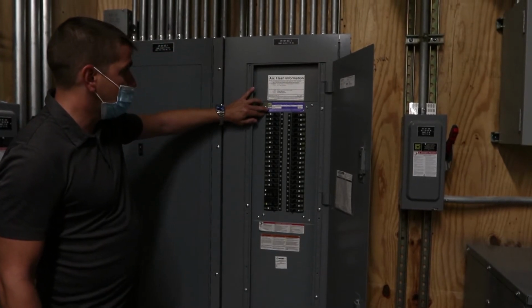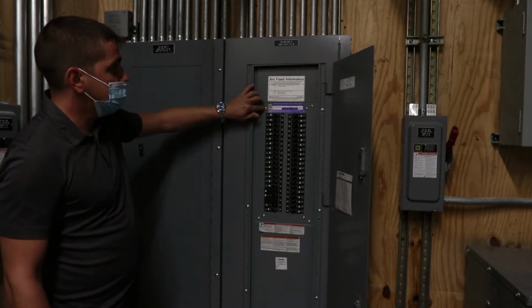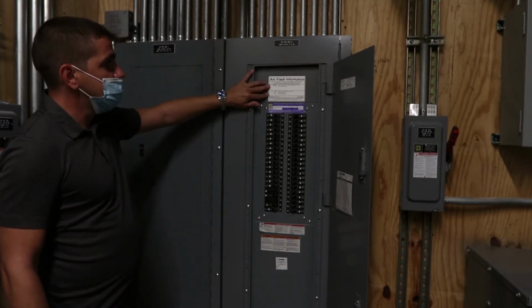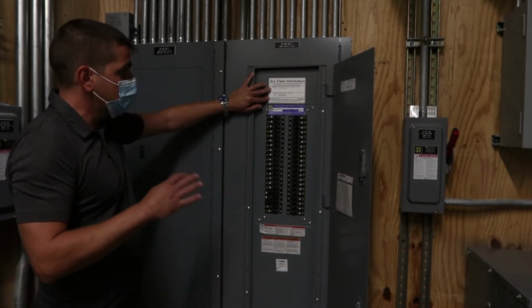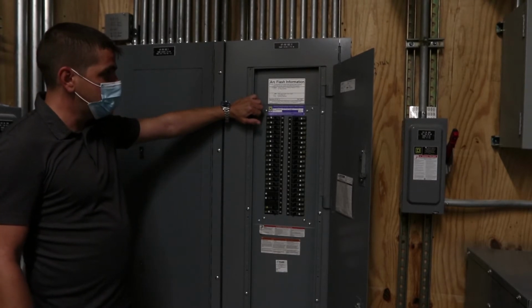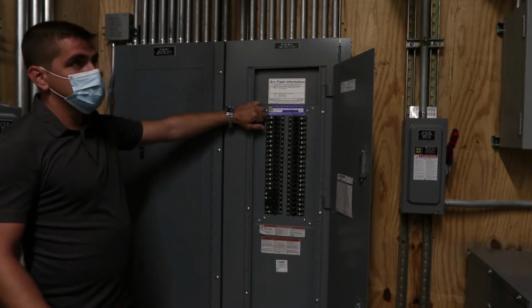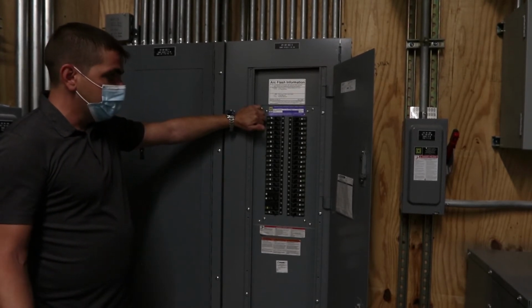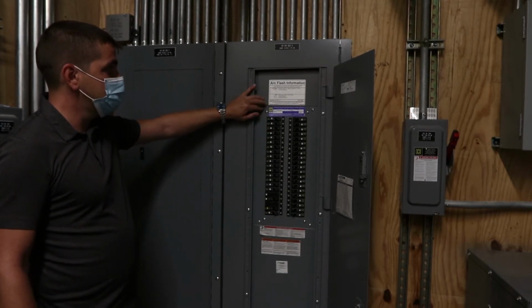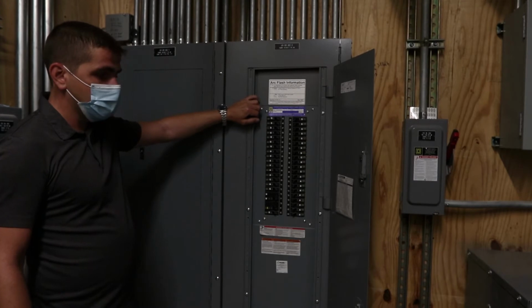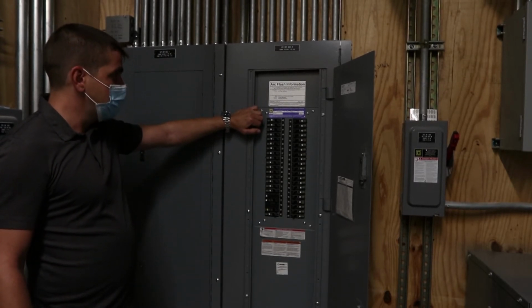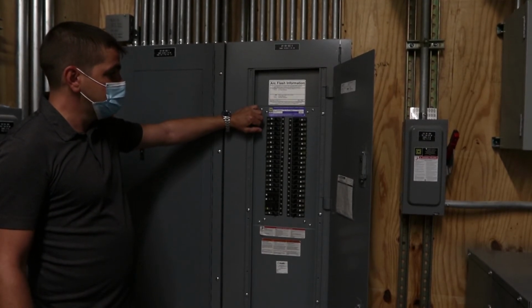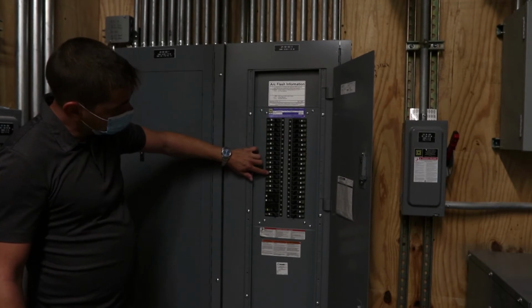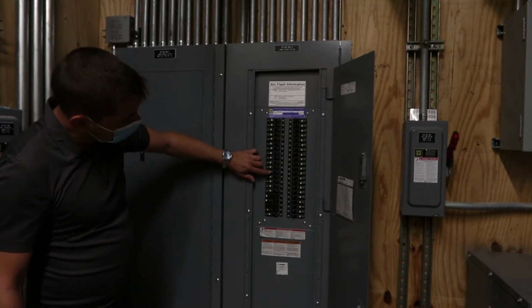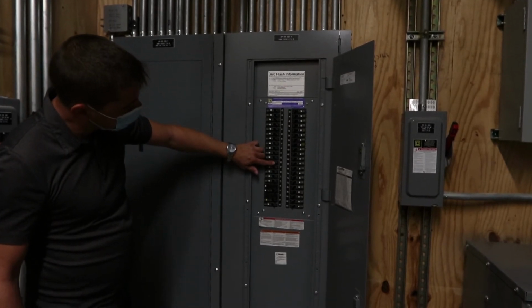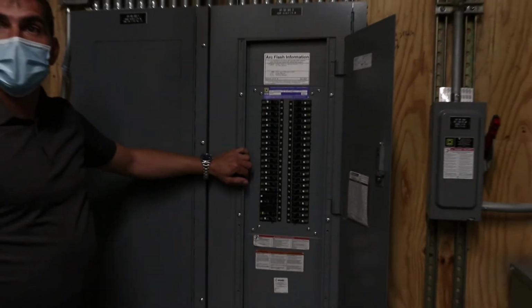All of the information on the voltage and amperage for the equipment is located on this nameplate. Also, the arc flash sticker indicates that work should not be performed on the equipment while energized, and if any work has to be performed, the equipment has to be de-energized from the distribution panel upstream. In the unlikely event that you would have to service it energized, all of the PPE based on the protocol of the facility has to be used. No specific requirements for the maintenance. Also, for simplicity of use, when the breaker is tripped, a little orange flag will pop out so you can physically see that the breaker is tripped. Other than that, that's it.